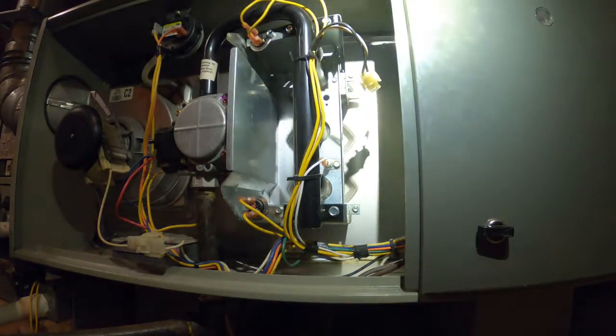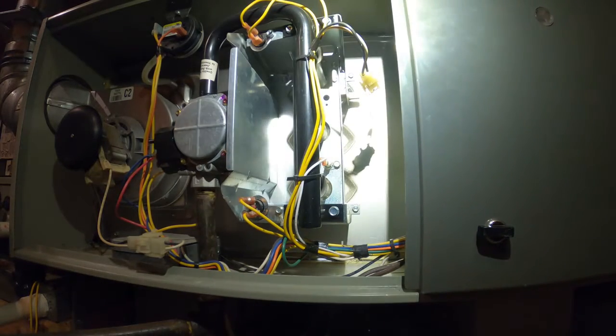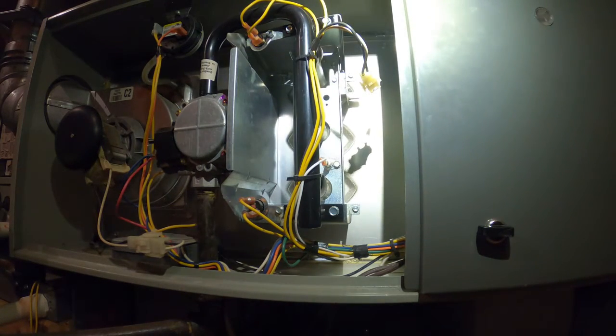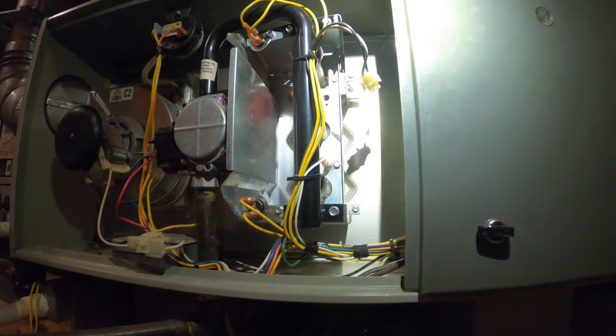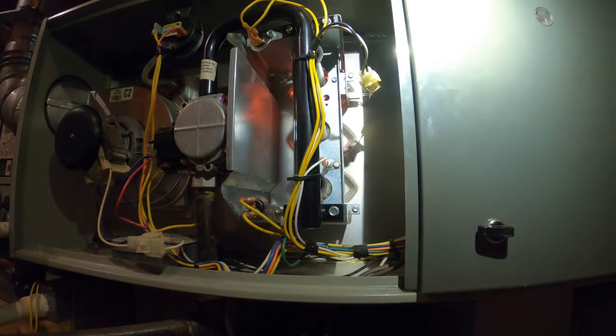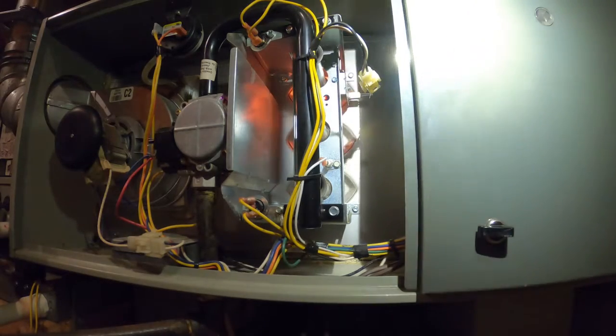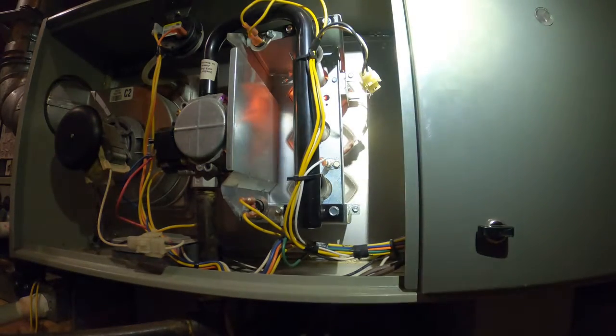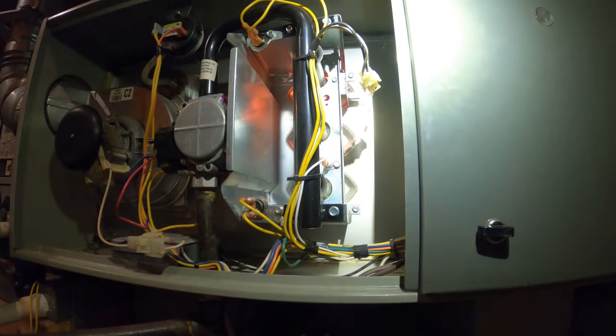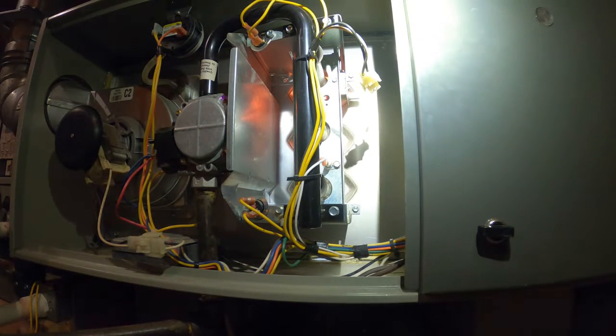I'm probably going to turn my light off so we can get a good visual of this and see what's going on when the blower cycles, and see what kind of issue we have with this heat exchanger, because if the flame's rolling out when the blower comes on, there is something fishy.